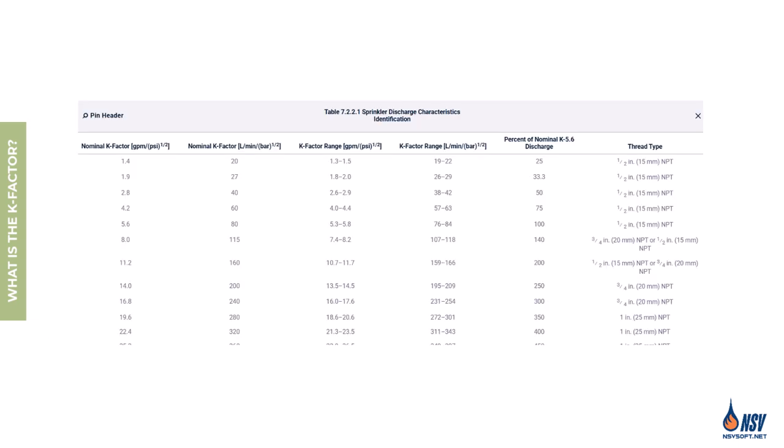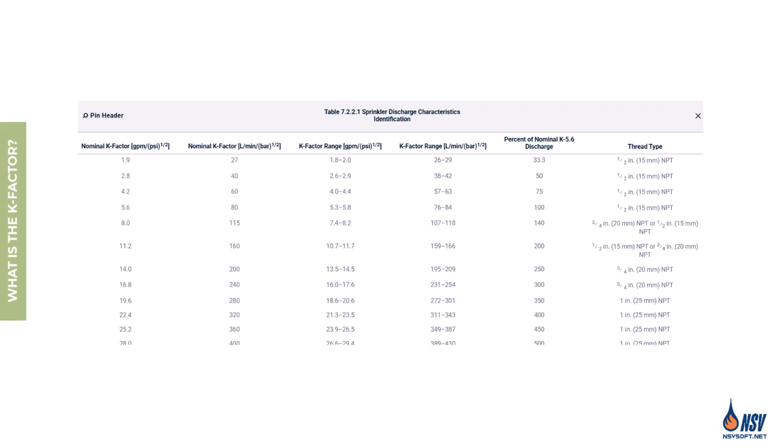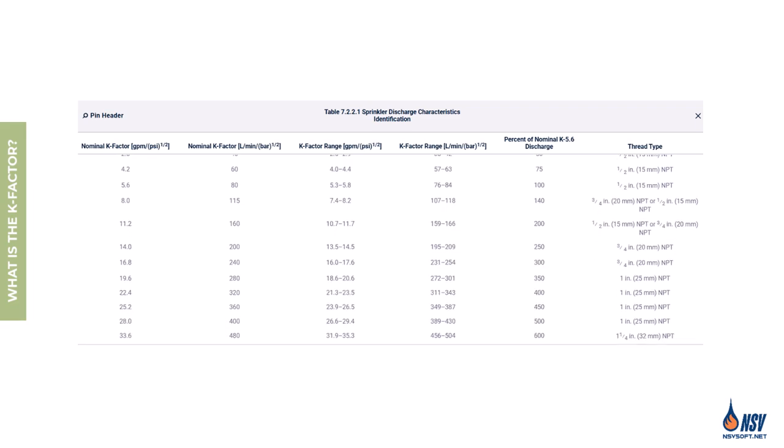In metric units, the K factor is expressed as liters per minute per square root of bar. NFPA 13 outlines the acceptable K factors for sprinklers in Table 7.2.2.1, and sprinkler manufacturers are required to comply with these specifications. Choosing sprinklers with the appropriate K factor is one of the most important aspects of system design — in some cases guided by NFPA 13 requirements, and in others left to the designer's discretion to optimize hydraulic performance.